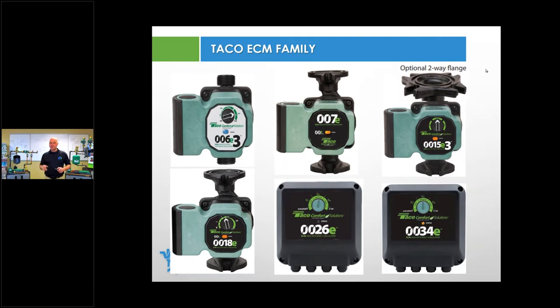007E. We have 007E. We have it in a two flange and a four flange footprint. The reason I'm pulling this one up is this is now stock OEM part on a lot of cast iron and condensing boilers. So your NTI in the condensing side, your Weil-McLain, your Burnham boilers, they're coming through standard. ECR products, they're coming through standard with an ECM 007E circulator. So we're going to dive into this 007E, make sure everybody's familiar with it.